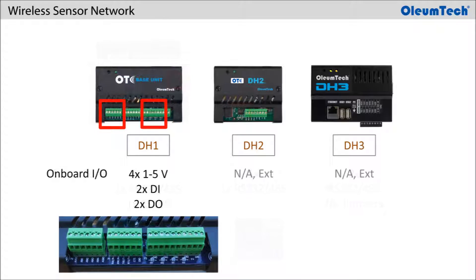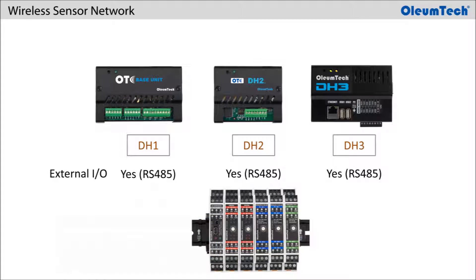Only the DH1 is equipped with onboard IOs, with four 1-5 volt analog inputs, two discrete inputs, and two discrete outputs. External IO expansion modules are available for use with all gateways.